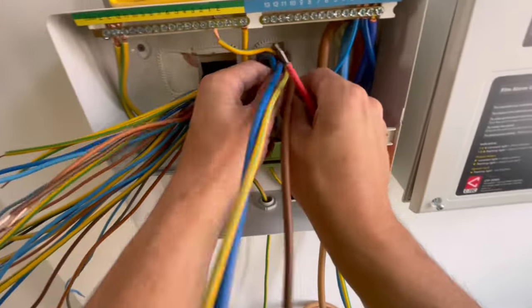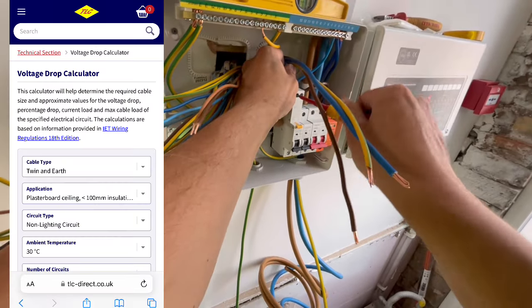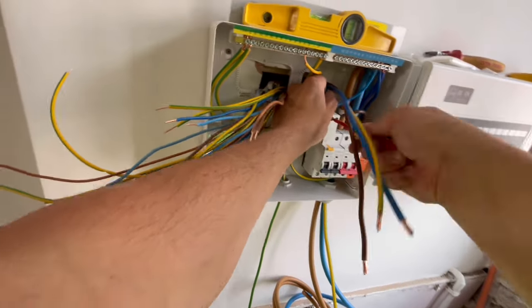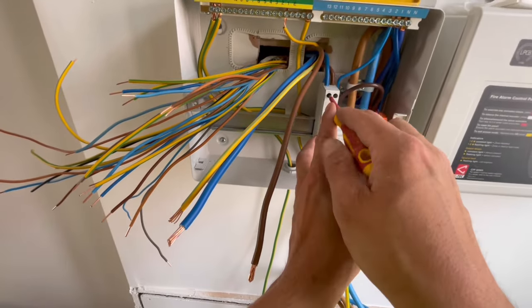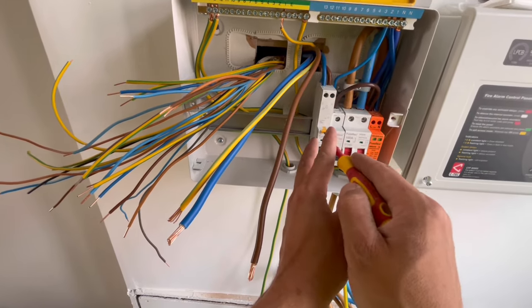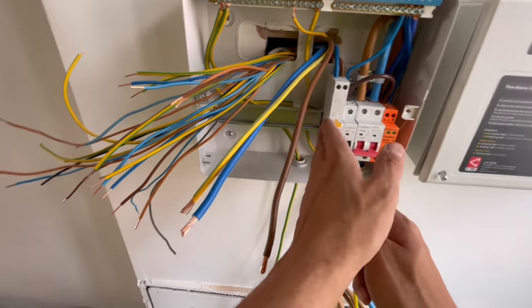So we've obviously done a calculation for the size of the cable, and you do learn that on your courses, however everyone just uses an online calculator these days, it'll do it for you. So, as you can tell, this now is connected. You've got your earth into there, your neutral and live, and this measures everything flowing between the neutral and live. And if there's any difference between these, obviously, if it's leaking somewhere else, either through a screw, water, or through a person, this will trip, but everything else will stay on.